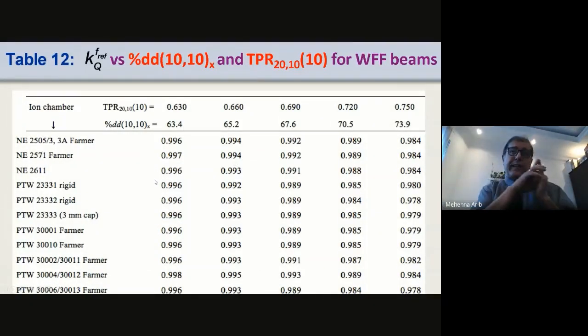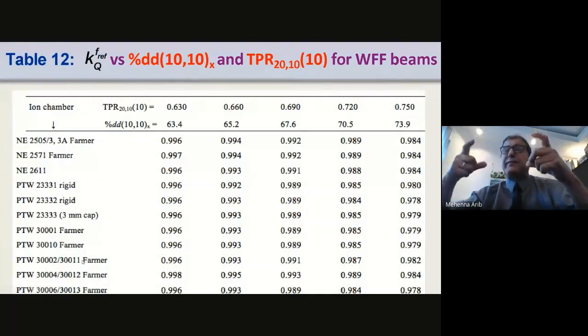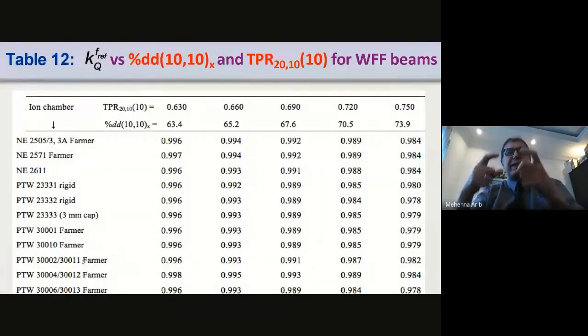Remember, when you measure the dose for the MSR field, you send the chamber to be calibrated at the calibration lab, SSDL or primary lab, and then you calculate the calibration coefficient using the conversion factor. The conversion factor is given as a function of TPR. Okay, so the problem is that this TPR is TPR 20/10, which is, as you know, measured for a field size of 10 by 10. You cannot achieve 10 by 10 for the MSR fields. You cannot have 10 by 10 with the CyberKnife, nor with the tomotherapy. So this is the first problem. How can you calculate the TPR 20/10, which is used to obtain your conversion factor for the reference dosimetry?